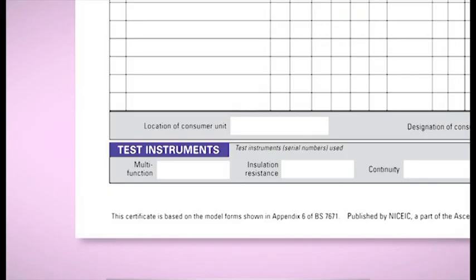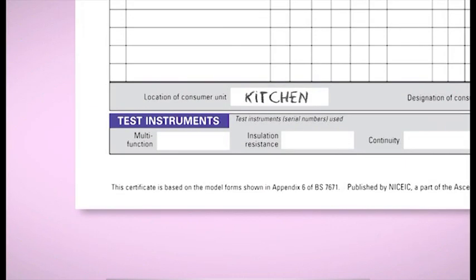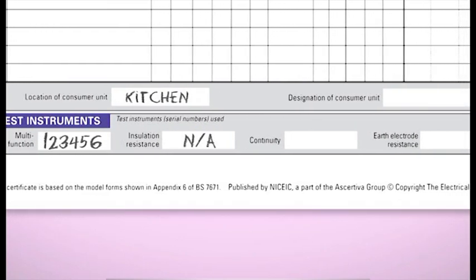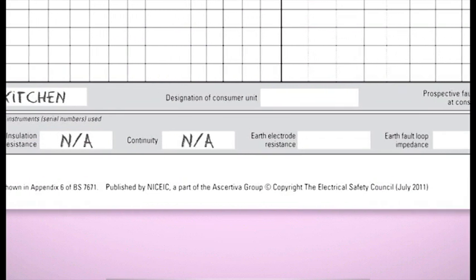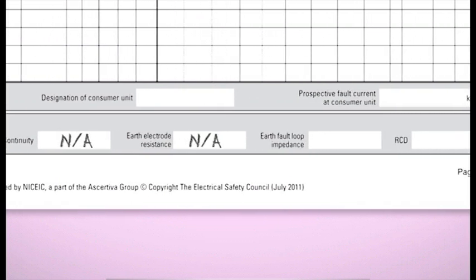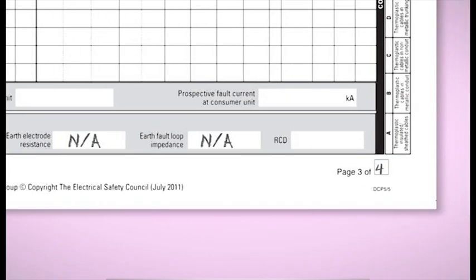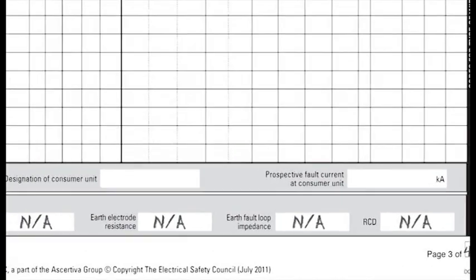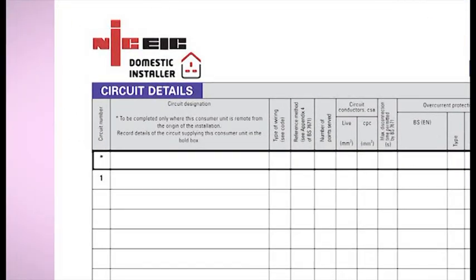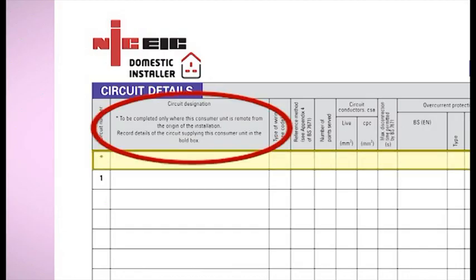Again, for this box, the location should be a recognisable description. For example, kitchen, garage or understairs. And finally, at the bottom of this sheet are boxes for the serial numbers of any test instruments used. This is vital as it allows for the instrument calibration history to be checked with the manufacturer if required. If you're using a multifunction test instrument, it's considered good practice to put NA in the other boxes. Actually, Dave, we should just quickly mention the first line on the schedules page, which is only to be completed where the consumer unit is remote from the origin of the installation. So we will put the details of the circuit supplying the consumer unit in here.